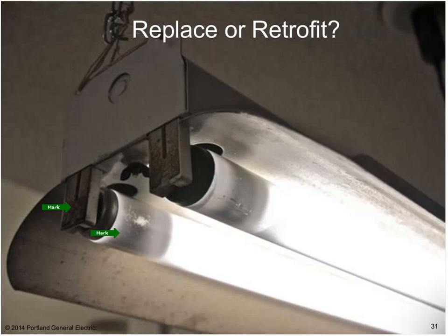But often you see these lamp holders, and I think you can tell in this picture it's kind of pushed out. That happens a lot with this type of fixture. Sometimes the lamps even fall out. But again, you can take this down to just the basic channel and put a new kit in, new reflector. Again, it looks just like new, but sometimes you want to just put a whole new fixture, especially if it's high up in the air.